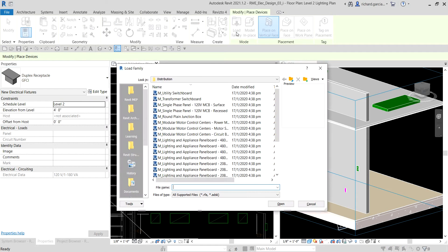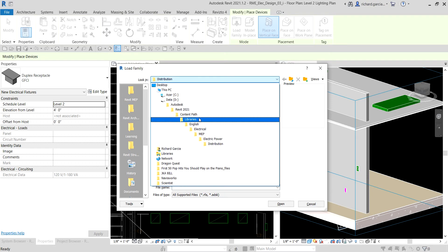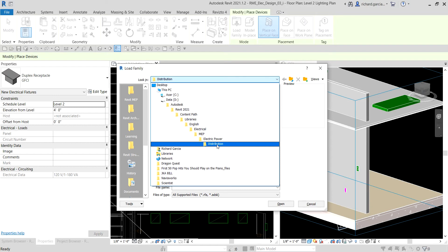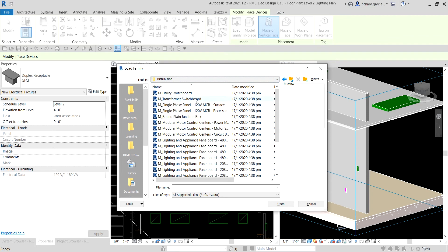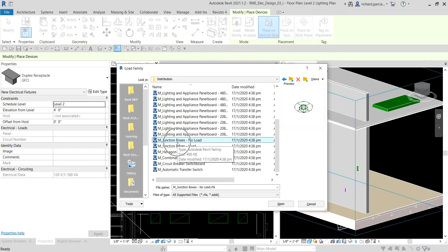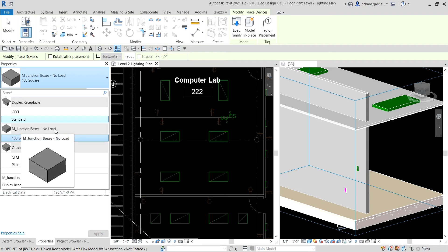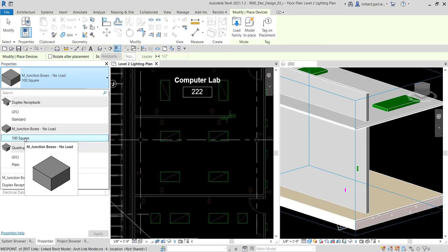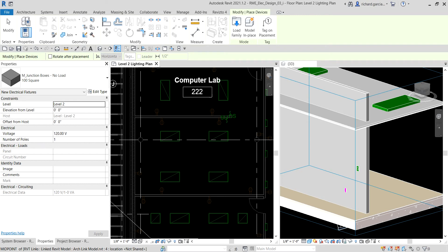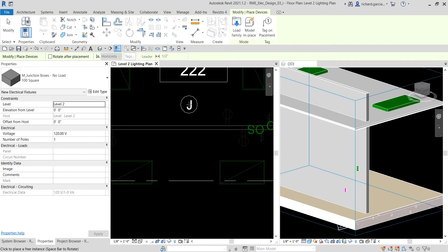I'm going to select Load Family and navigate to English > Electrical > MEP > Electric Power > Distribution. I'll look for a panel junction box — I'll select 'M Junction Boxes No Load,' then select Open. From the family, I'll choose 'M Junction Boxes No Load, 100 Square.' We're now going to place it. This is a non-hosted family, so there's no option for 'Place on Vertical Face' or 'Place on Face' — I can just place it directly.